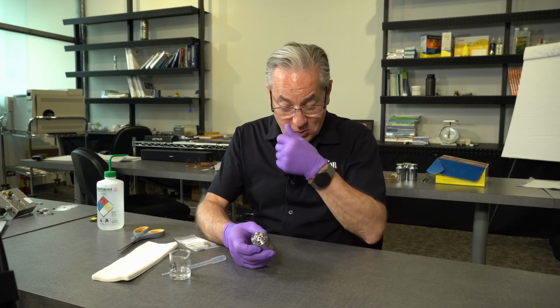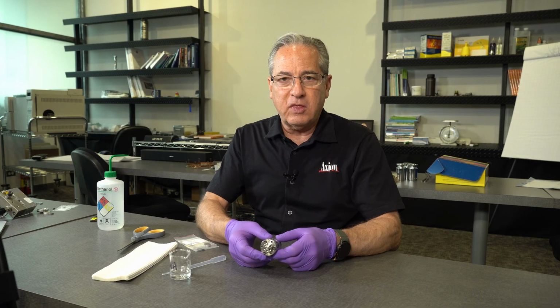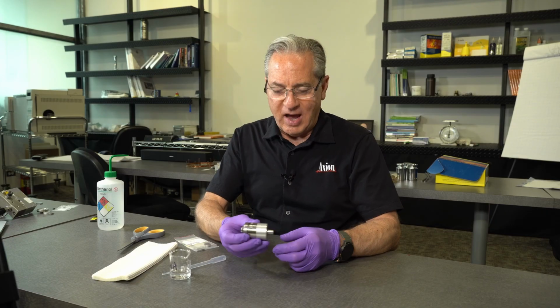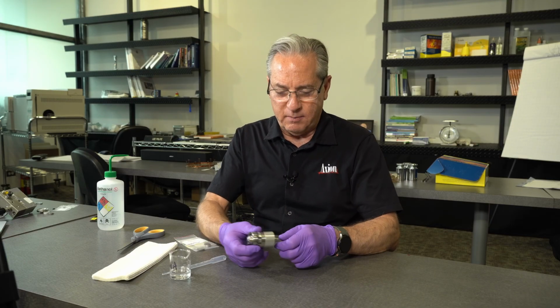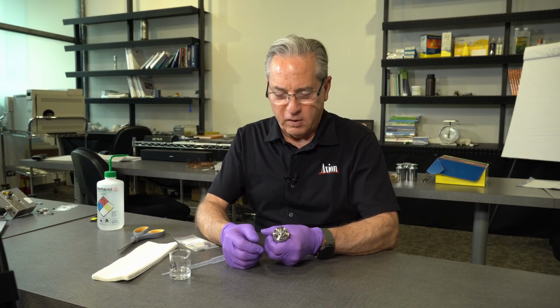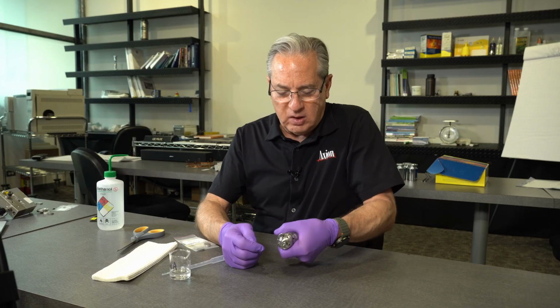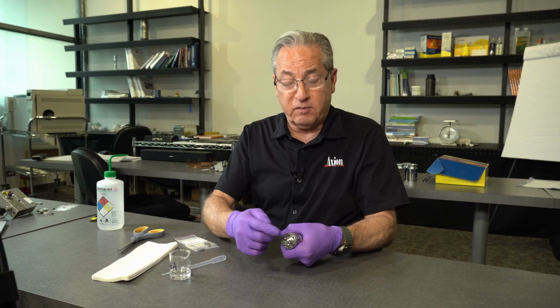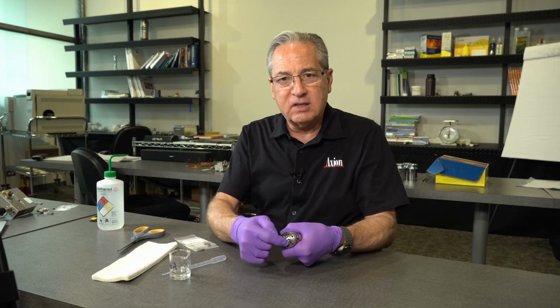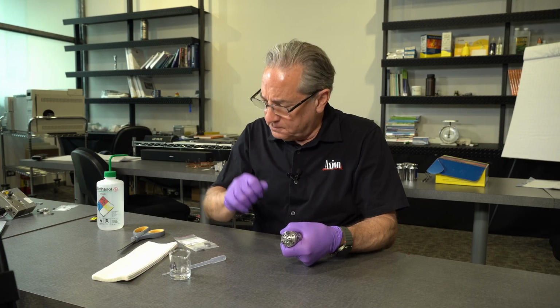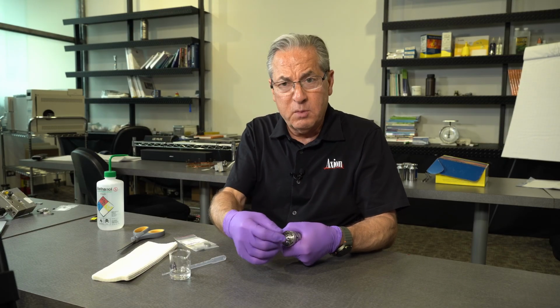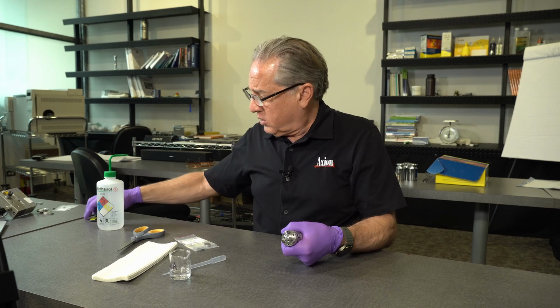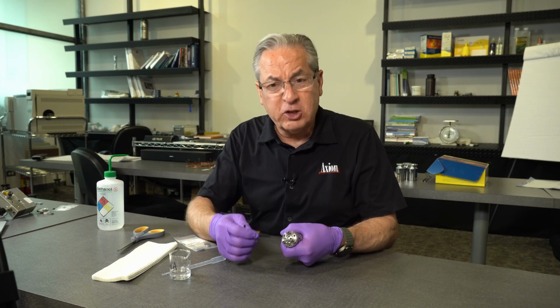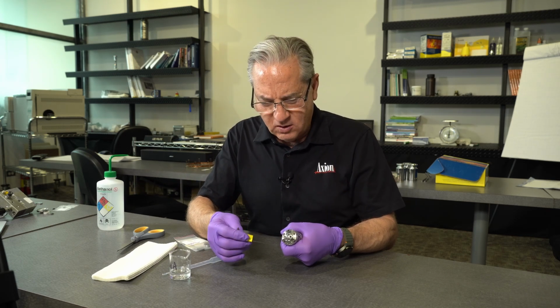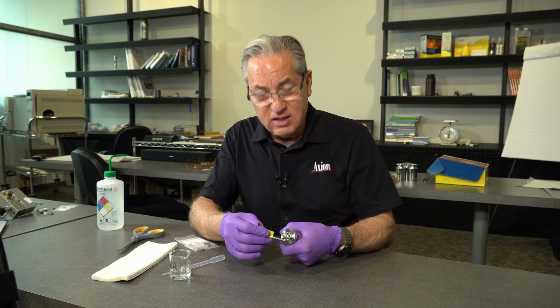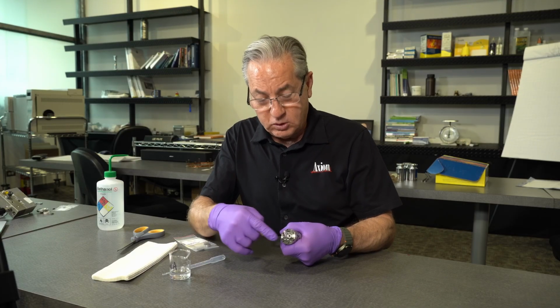So to dismantle this, you could do this with this still in the instrument. I have one that I've taken out of the instrument, to give you a better feel for what you're about to do. But usually this is mounted in the instrument. This part is facing out. There are 6 pieces of tubing that are going in here. So you could either remove all 6, or with a little bit of luck, you can actually try and disassemble it with the tubing still on there. Officially, you're supposed to take the 6 fittings out first, which is what we've done.